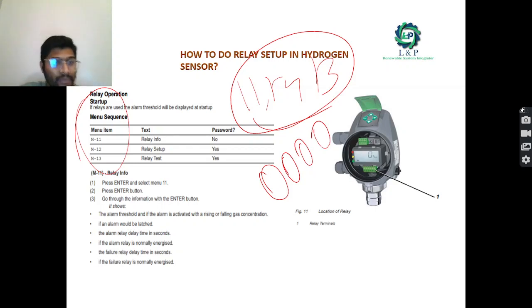Okay, as we told earlier, if you get into menu 11, what can you see? It shows the alarm threshold, whether the alarm is activated with rising or falling gas concentration, whether an alarm would be latched, what the delay timing is, whether the alarm relay is in the normally energized mode, what the failure relay delay time in seconds is, and how the failure relay is normally energized. All sorts of information will be available in menu 11.